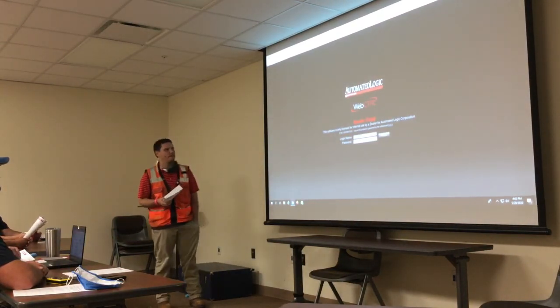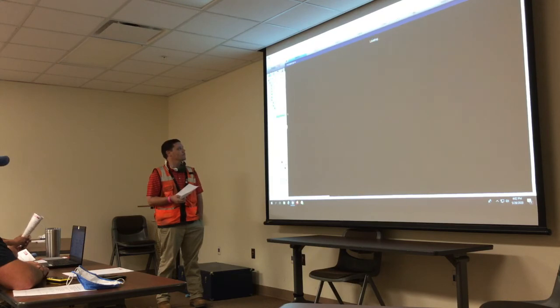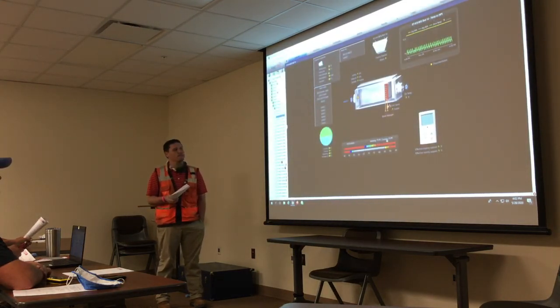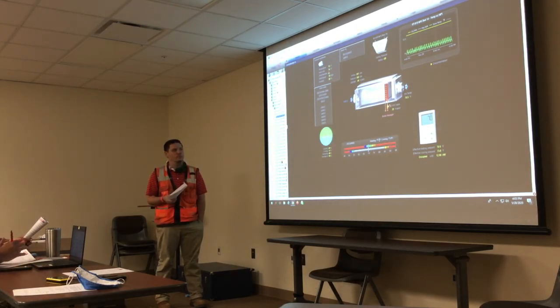No. What can we go plus or minus 4 degrees from? It's plus or minus 4 degrees of the set points. So it's plus or minus 4 degrees of this. Heating 70, cooling 73. So we can go up to 74, 77, or down to 66, 69. So the whole thing moves. If I move it down minus 4 degrees, we would be 66, 69 for our set points. If I move it back to 0, we'll be 70, 73. If I move it up 4 degrees, I'd be 74, 77. So the whole band moves.